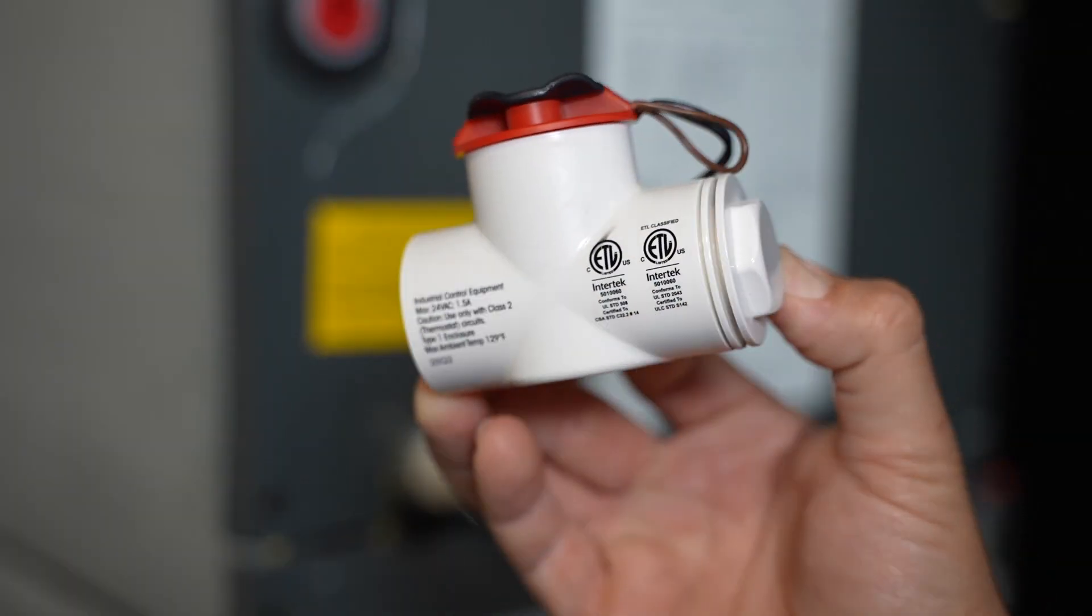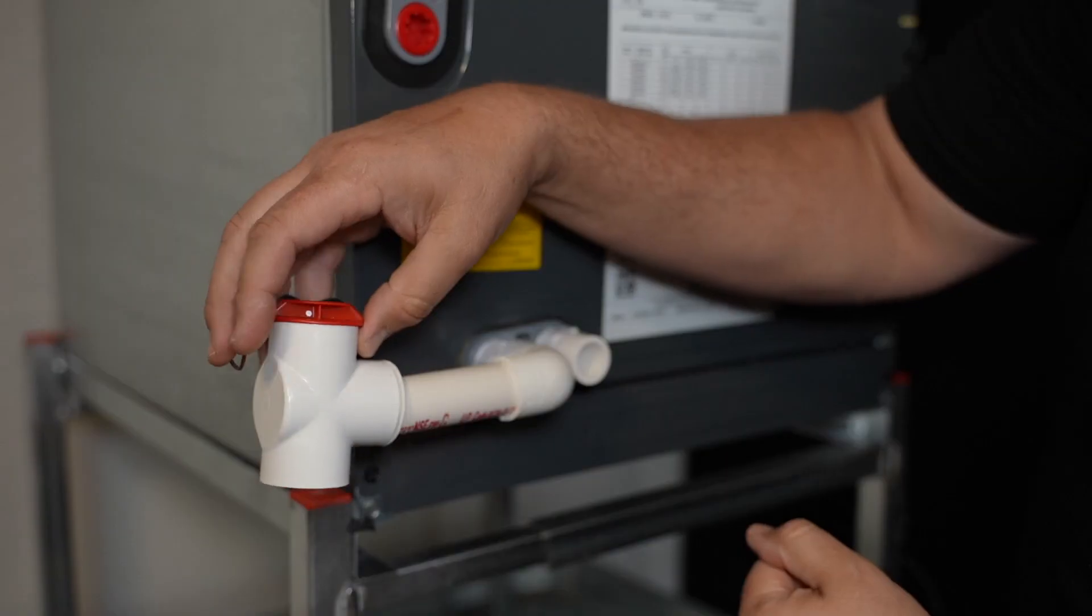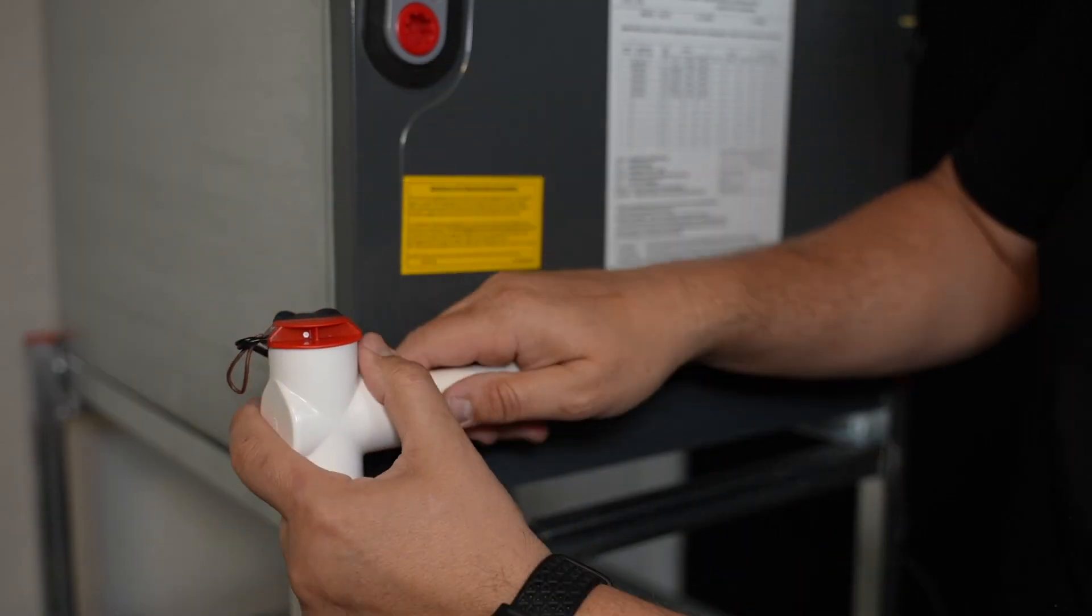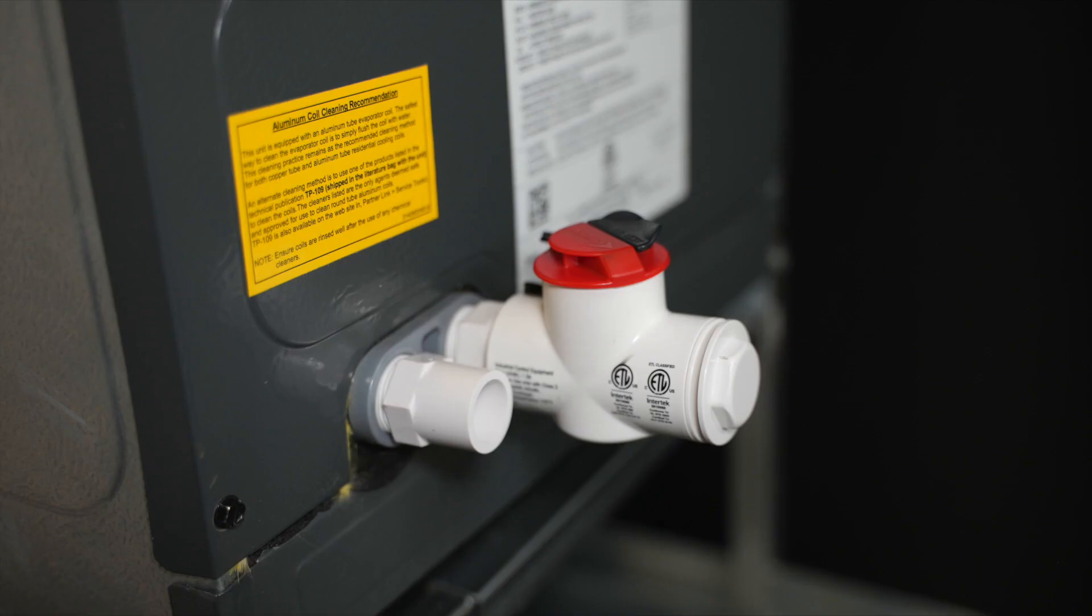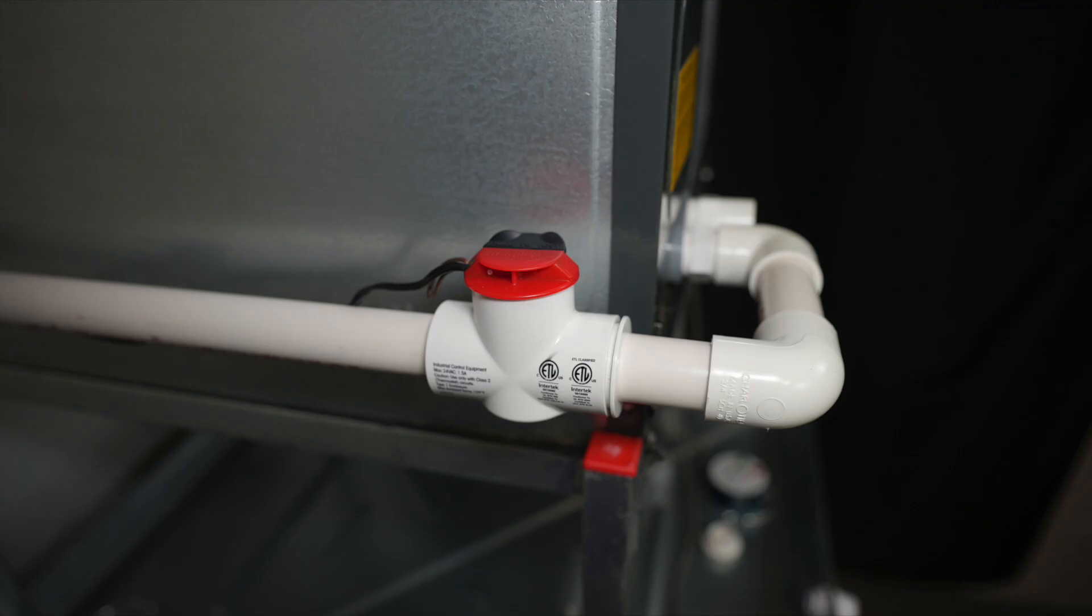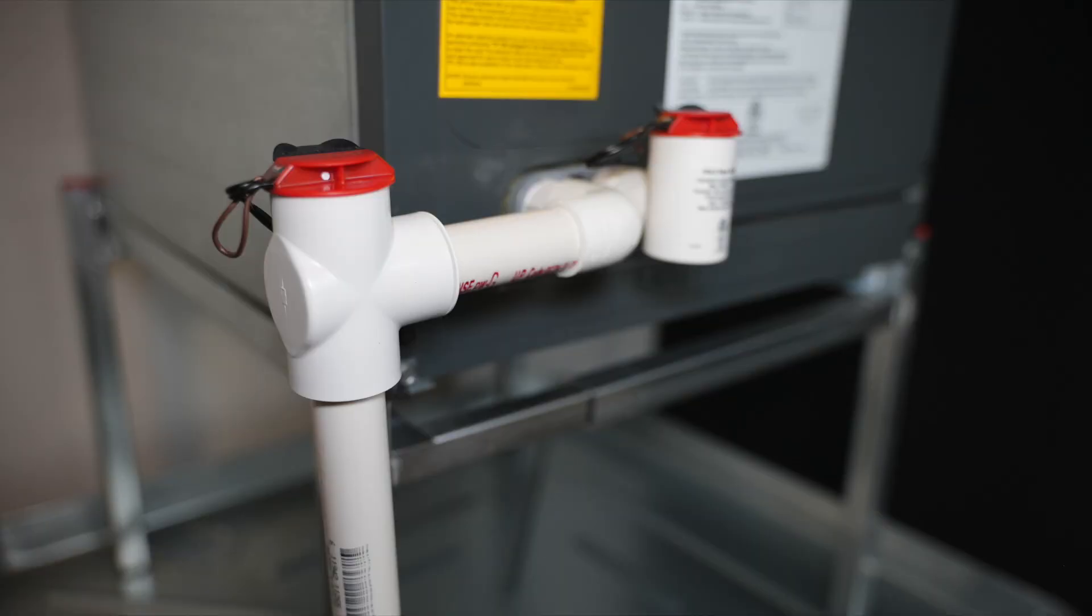The CS1 condensate overflow switch is a versatile option for primary or secondary drain line applications. It has three install configurations: primary pan secondary port, primary pan main port in the horizontal drain line, and primary pan main port in the vertical drain line.